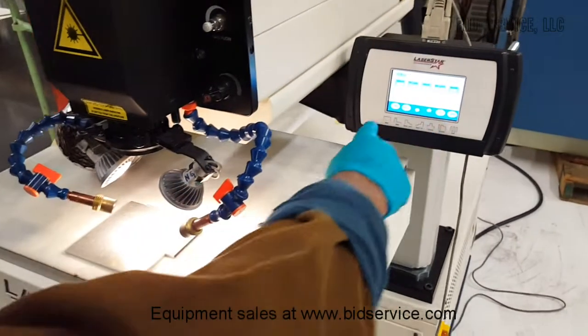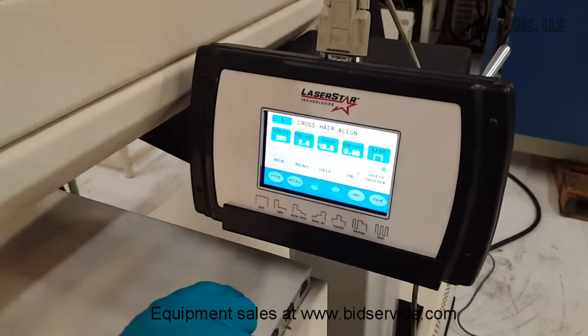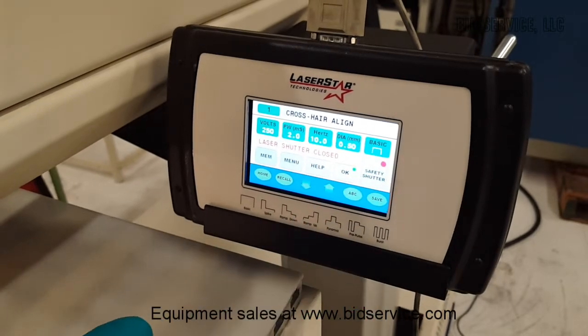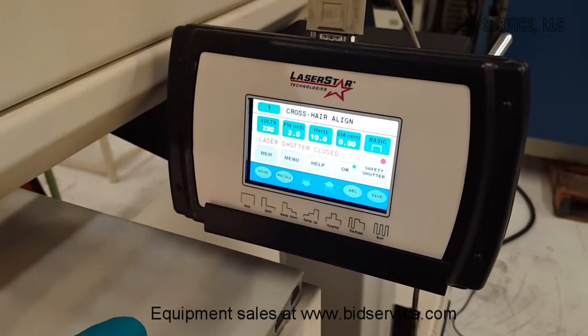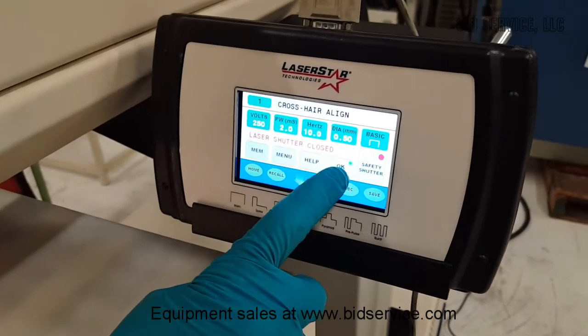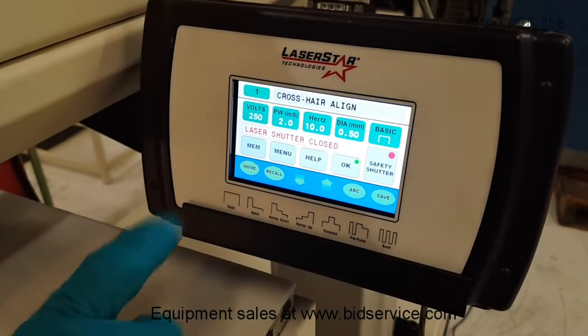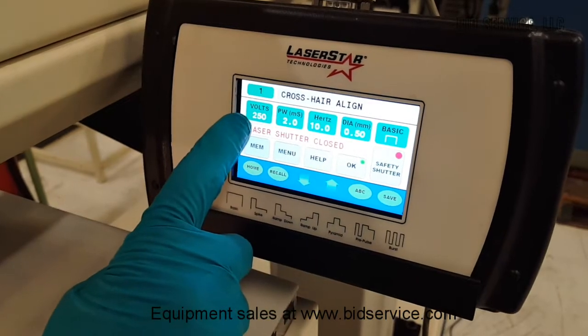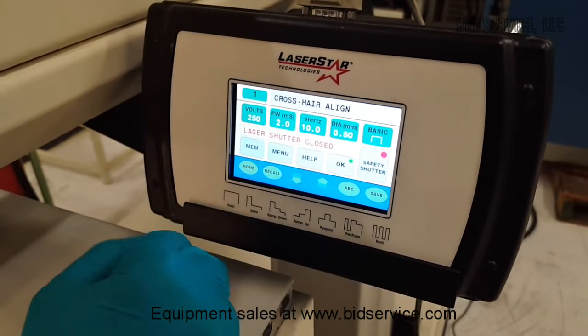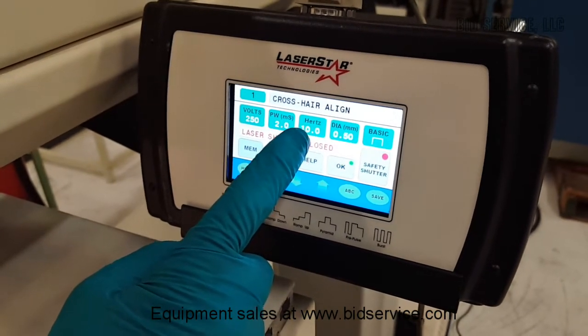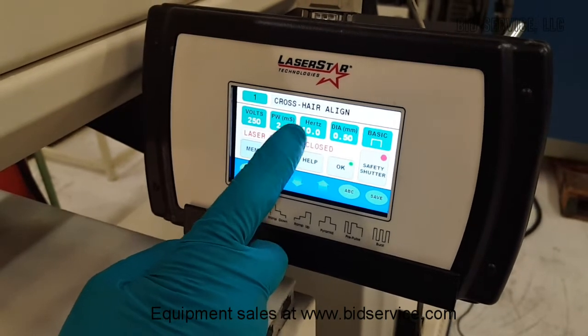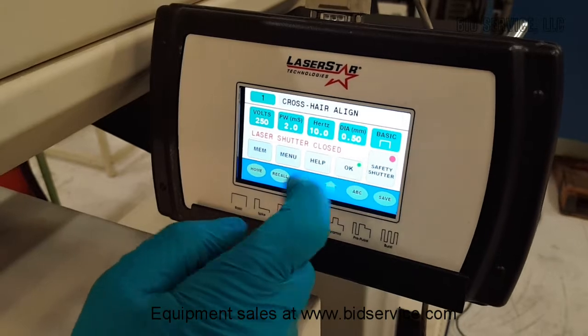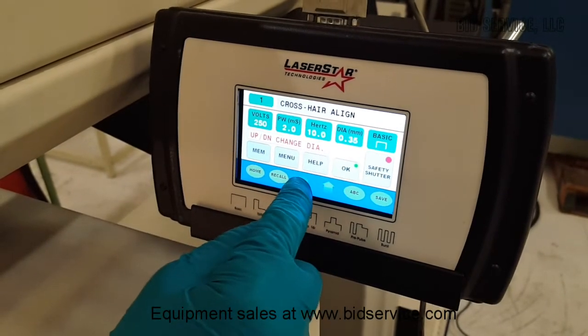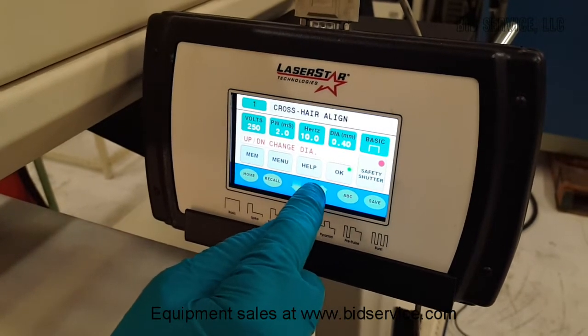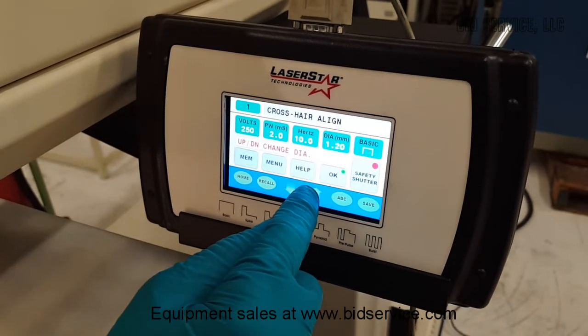The system is controlled from this touchpad screen. On power on, the system will boot up, and it takes about a few minutes before the OK turns green here. On the touch screen, the laser parameters can be varied, such as voltage, pulse width, and pulse duration, or the burst mode or hertz can be selected. Also the diameter can be changed from as low as 0.2 millimeters up to as high as 2 millimeters with the current setup in this machine.